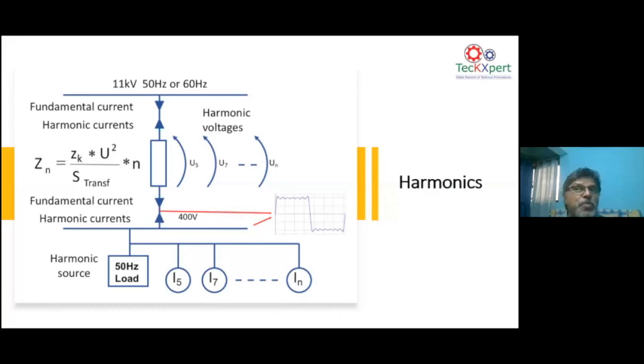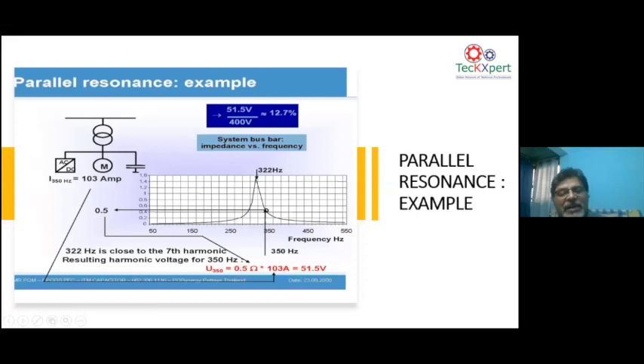Because as you know, 2 pi FL, the frequency is an important factor in deciding the impedance value, whether it's inductance or capacitance. So that means here, when there is a 100 ampere current, harmonic current generated by this drive, if there is a resonance happening, then you can see there is a seventh harmonic voltage drop of 51.5, which is 12.7. So that means you can see this is a parallel resonance problem.